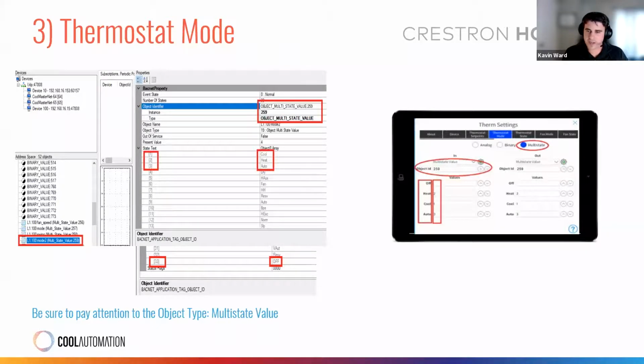In your drop-down for in and out, both are multi-state values, so we enter 259. Then we need to find the actual object array to identify between cooling, heating, auto, and off. Off is all the way at the bottom, typically number 33. So under multi-state value 259: off is 33, heating is 2, cooling is 1, and auto is 3.